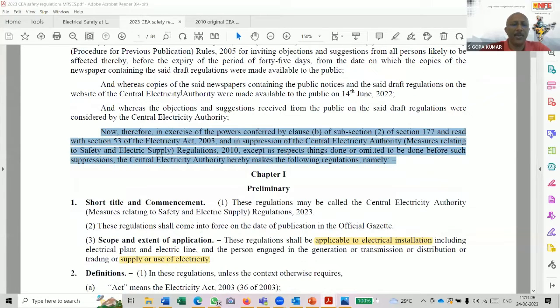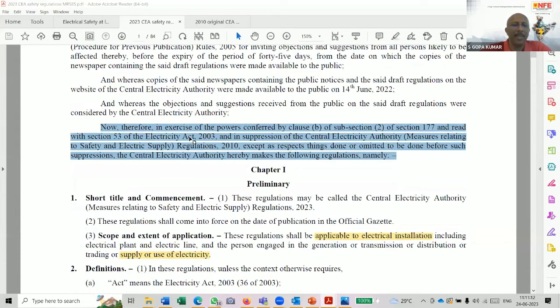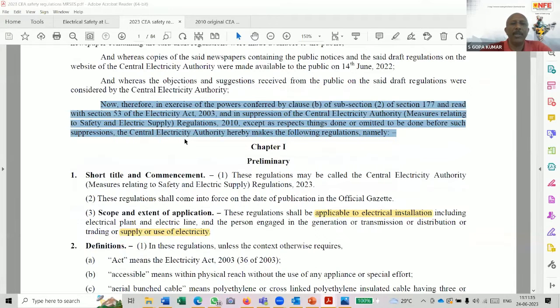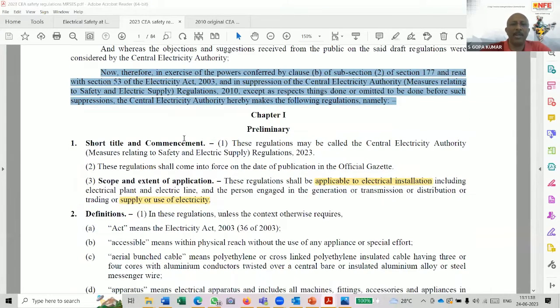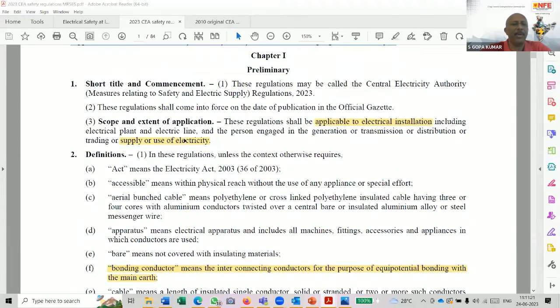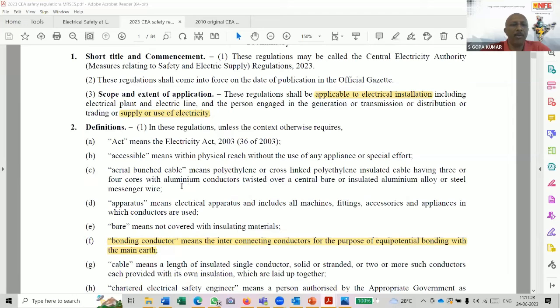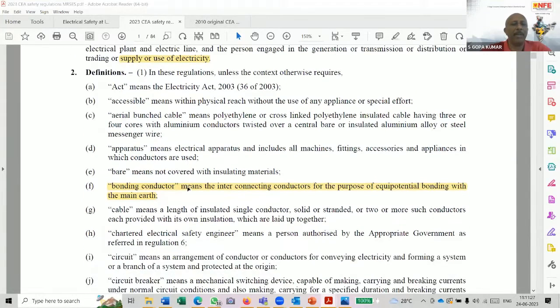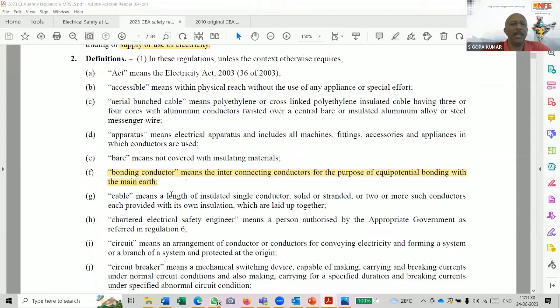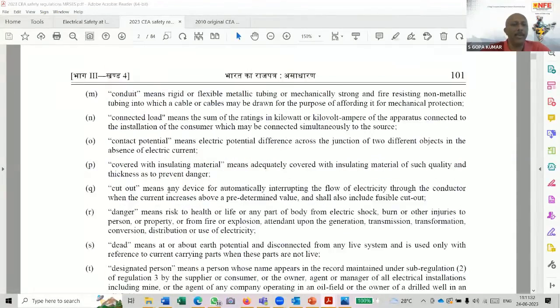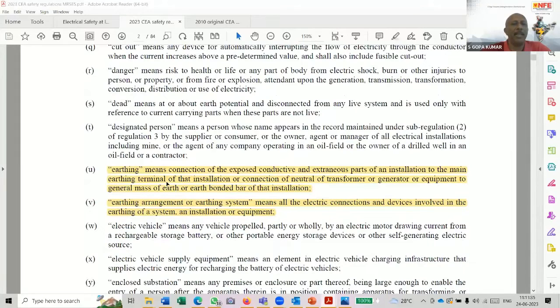Thank you very much. As the panelist, my first question is to Mr. Amrit Lal. On the screen, I'm showing the regulation. I'm sure you and all of us must have read most of the regulations. One of the confusing subjects all over India was earthing, and definitions sometimes were not good. Now in the regulations, for example, you can see bonding conductor has a new definition. And earthing also has a new definition: earthing means connection of exposed conductive parts and extraneous conductive parts to the earthing terminal. So all of this has come. What is your opinion about these new definitions?